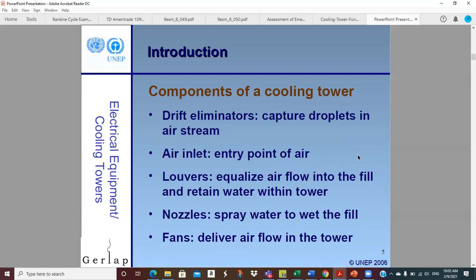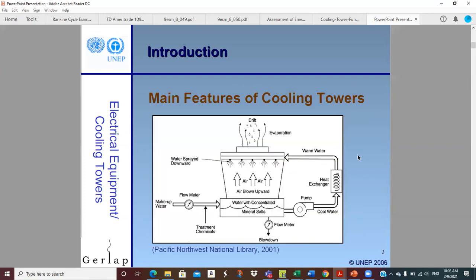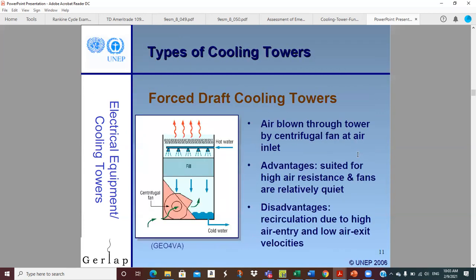Okay, drift eliminators. So up at the top of the tower, we've got some better pictures here. These little crinkly guys up here at the top are some sort of sheet metal, or probably heavy duty plastic these days. The idea is the air is being blown up through here at significant velocity, and it's carrying these droplets with it. Well, we want to keep the droplets inside the tower. So we make the air change direction a couple of times. It goes up a little bit, and it goes sideways, and then it goes up and sideways a couple more times. The droplets hit the sides, so most of the droplets hit and coalesce on the drift eliminators, and then they fall back into the tower. So that's what a drift eliminator is. These days, if you buy a tower, it's going to have a drift eliminator on it.